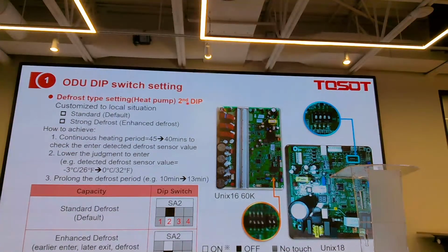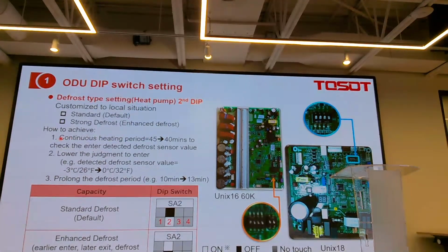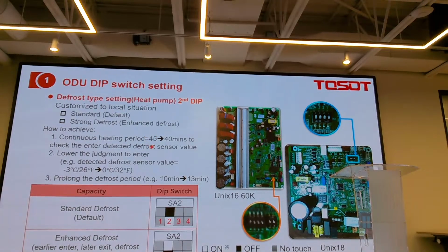As for the second DIP of this Unix18, that is how to do the defrost. We have the standard one and also the strong one, also called enhanced defrost. What is the difference between these two? For the enhanced defrost, we make the defrost more complete by adjusting parameters like the continuous heating period, making it shorter. For the standard one, let's say it judges every 45 minutes whether the conditions are satisfied to do the defrost or not. But for the strong or enhanced defrost, it judges every 40 minutes. And the condition is the defrost sensor value, which is this one.